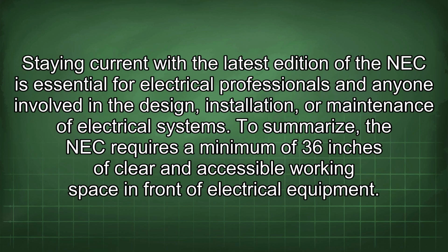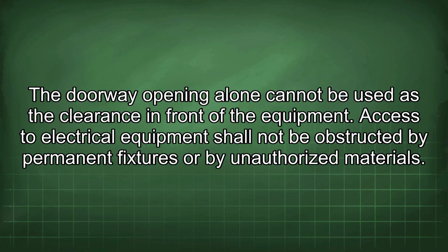Staying current with the latest edition of the NEC is essential for electrical professionals and anyone involved in the design, installation, or maintenance of electrical systems. To summarize, the NEC requires a minimum of 36 inches of clear and accessible working space in front of electrical equipment. The doorway opening alone cannot be used as the clearance in front of the equipment. Access to electrical equipment shall not be obstructed by permanent fixtures or by unauthorized materials.